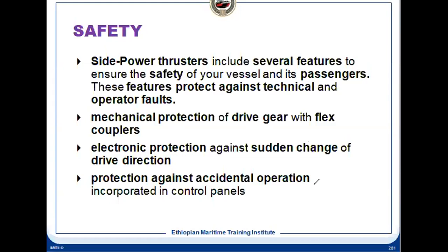It means suppose it is a gear arrangement, then there will be a flexible coupling, because the driven side is by the gear with a different speed. So in that case, the flexible coupling has to be used, so that the coupling will take the load. If something goes wrong, the coupling will get damaged, not the pump or the motor.